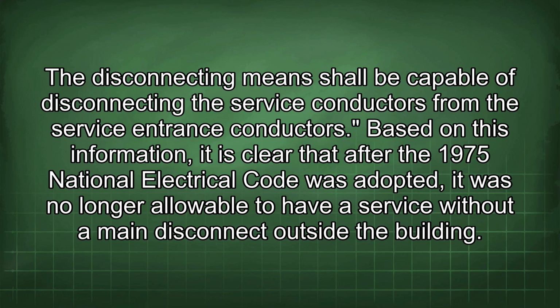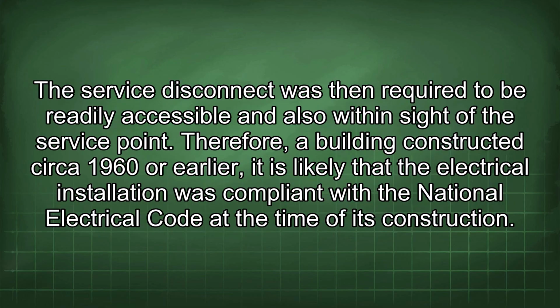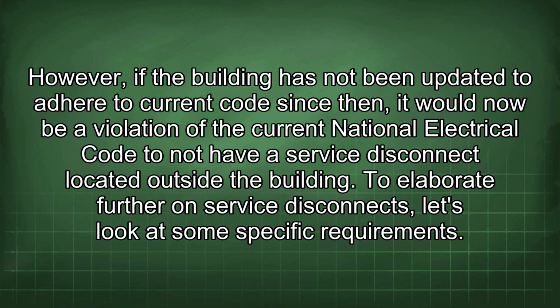Based on this information, it is clear that after the 1975 National Electrical Code was adopted, it was no longer allowable to have a service without a main disconnect outside the building. The service disconnect was then required to be readily accessible and also within sight of the service point. Therefore, for a building constructed circa 1960 or earlier, it is likely that the electrical installation was compliant with the National Electrical Code at the time of its construction. However, if the building has not been updated to adhere to current codes since then, it would now be a violation of the current National Electrical Code to not have a service disconnect located outside the building.